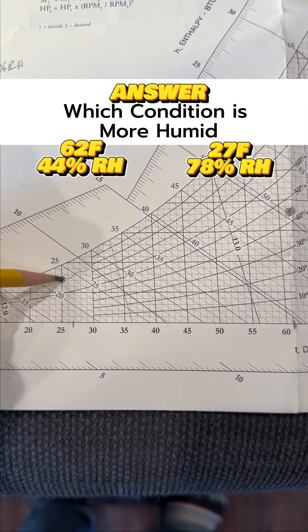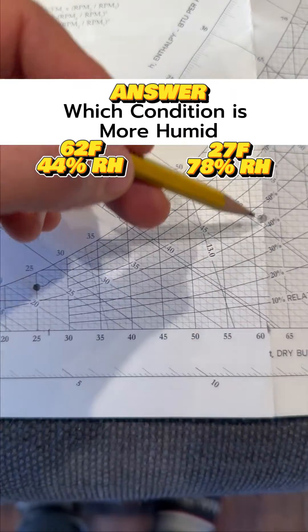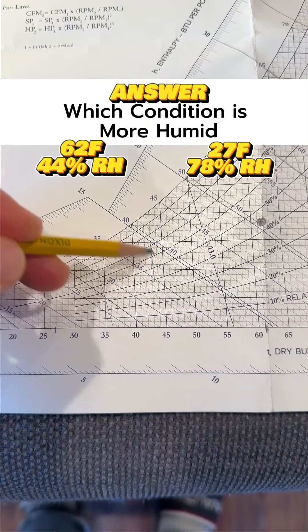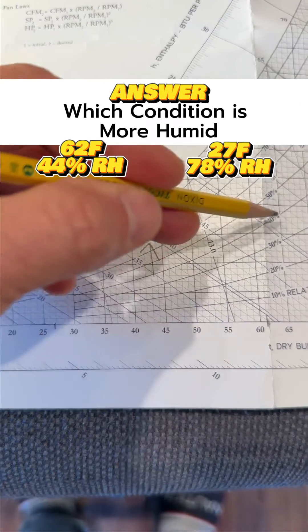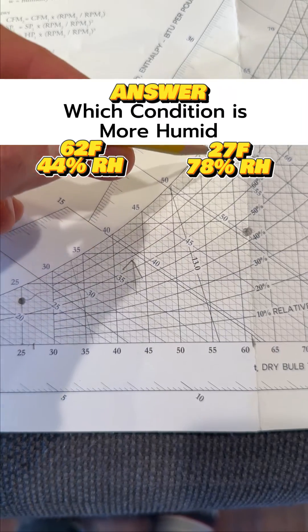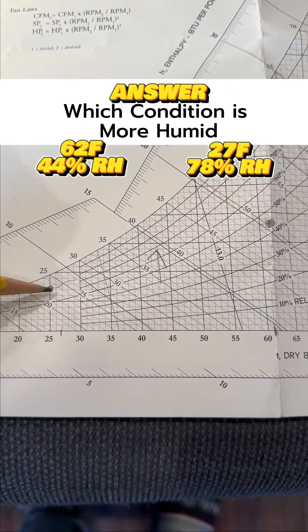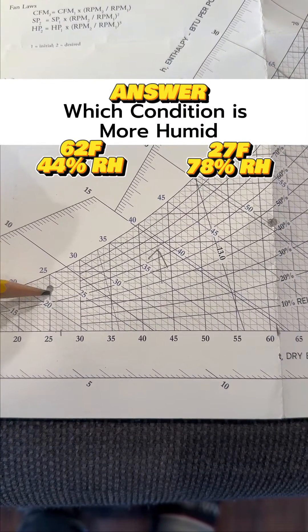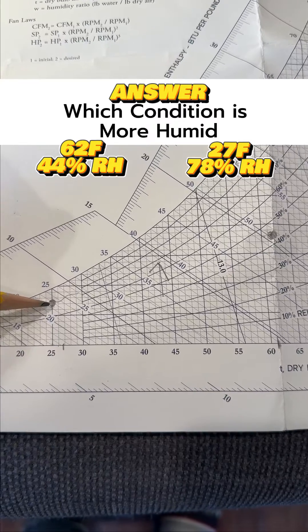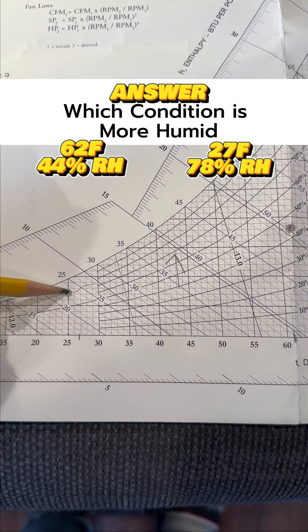Now, just for purposes of this, we know that this condition here is more humid because it's higher on the psychrometric chart. And as we go up in this way, we add humidity to the air. So relative humidity is not a good indicator when you're comparing two points of which one has more humidity.